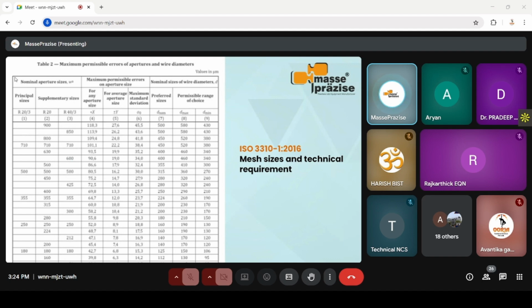Second part is nominal sizes of wire diameter. Wire diameter is denoted in nominal size of 710. For 710 micron, it is 450 micron, and the range is from 380 to 520 micron. Basically, 450 plus or minus 15% is the range. So we have a criteria of plus or minus 15% for wire diameter from the nominal value. This is the basic requirement of ISO 3310 for any mesh size.